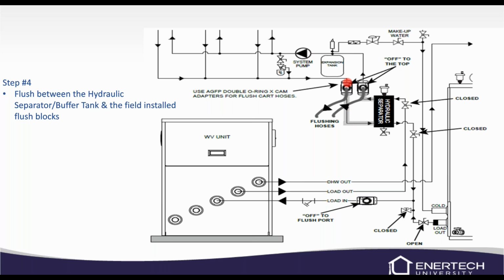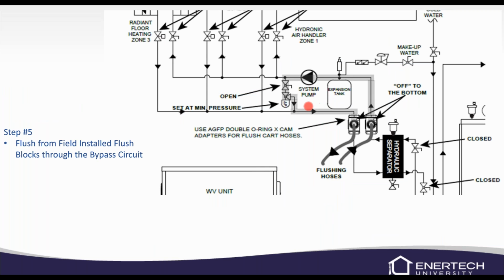Now, if you have this hydraulic separator or your buffer tank installed, in order for the system or your zone pump not to deadhead, we will have a second bypass valve here. So the next step is we're going to flush that bypass valve circuit. We're going to flush out through the bypass and back through. It shouldn't take real long. Again, that bypass valve is there to protect the system pump from deadheading if none of your valves open up.